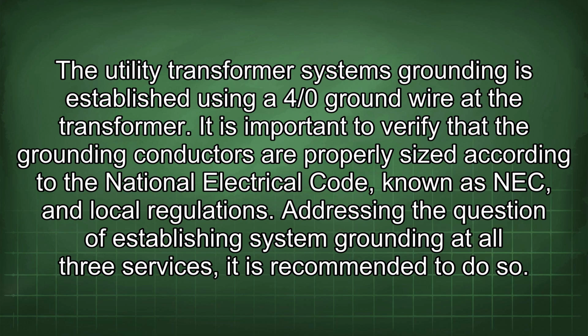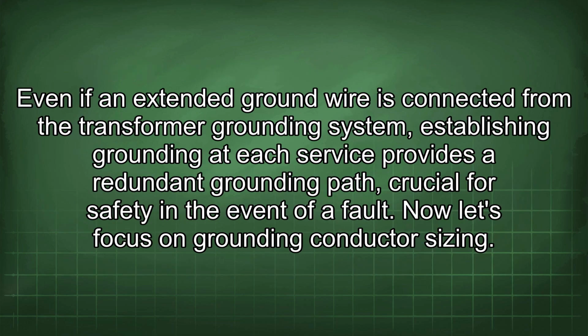NEC, and local regulations. Addressing the question of establishing system grounding at all 3 services, it is recommended to do so. Even if an extended ground wire is connected from the transformer grounding system, establishing grounding at each service provides a redundant grounding path, crucial for safety in the event of a fault.